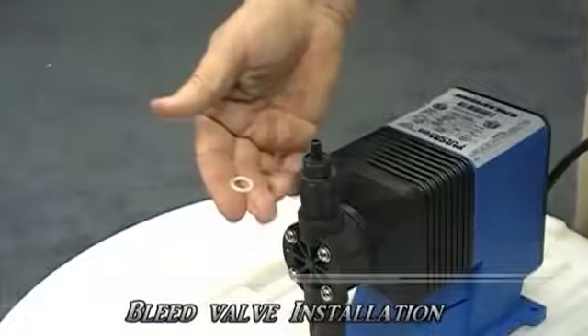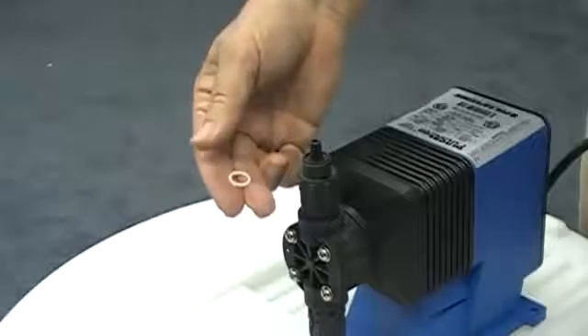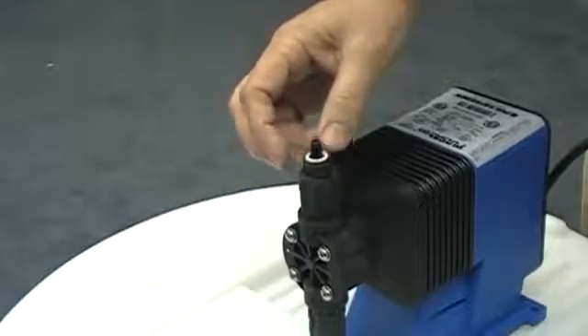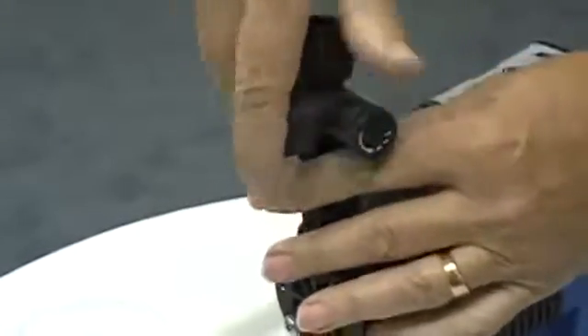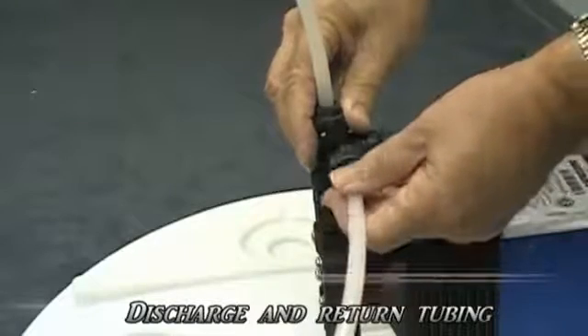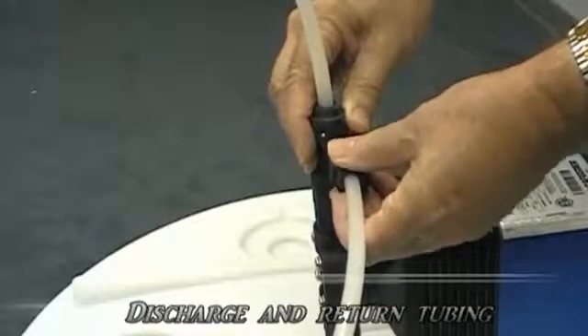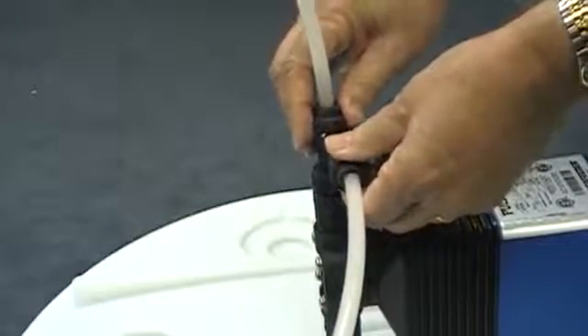The first step of installing the discharge tubing is to install the bleed valve. There is an O-ring in your accessory kit, which is installed in the discharge valve groove. Then the bleed valve is attached to the top of the discharge valve. The discharge tubing is connected to the top of the bleed valve. The return tubing is connected to the side of the bleed valve and then placed in the top of the tank. All of these fittings are to be tightened hand-tight.